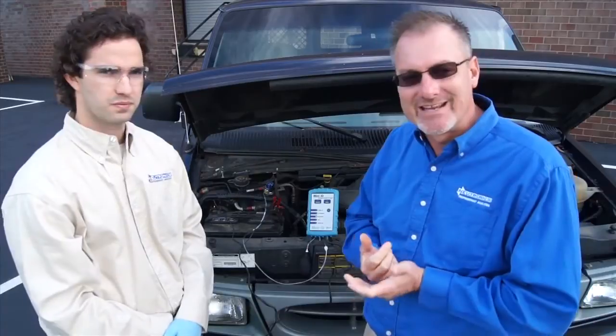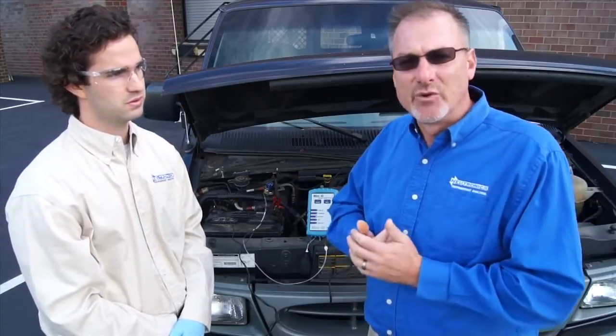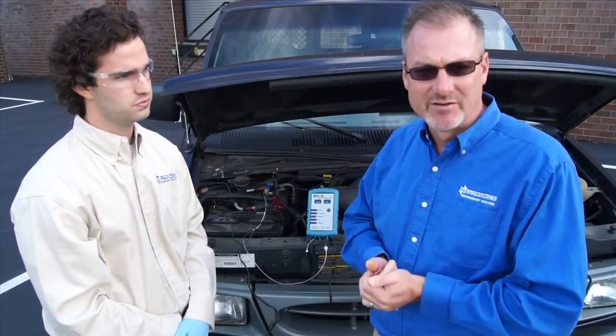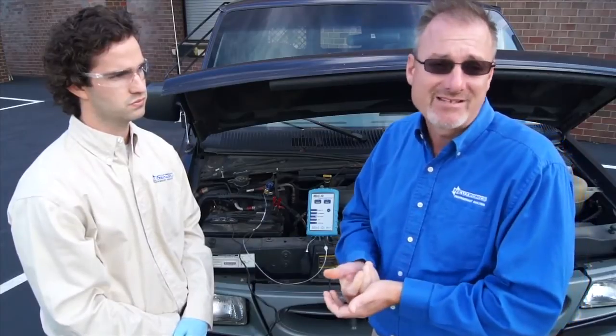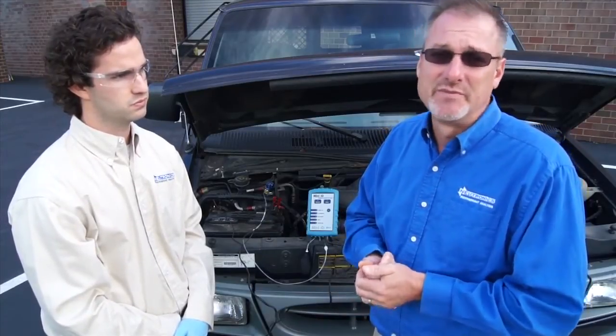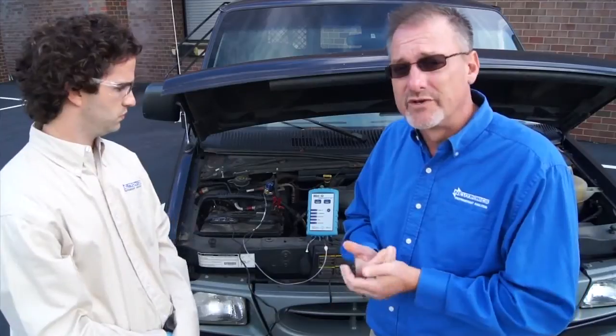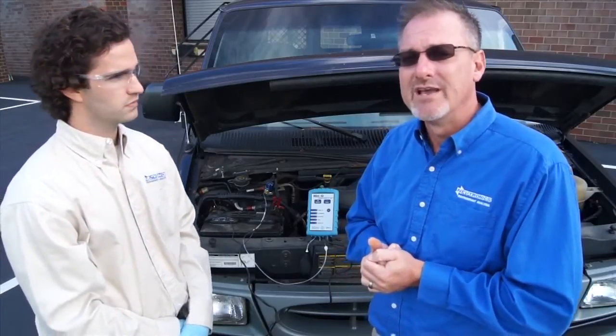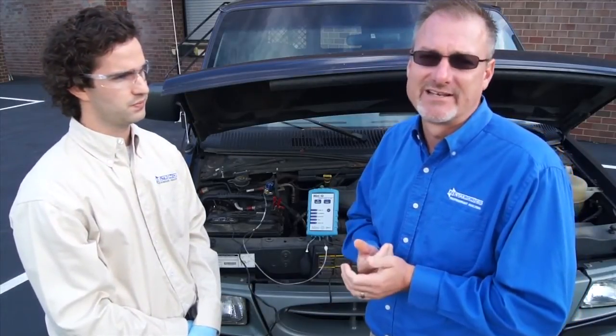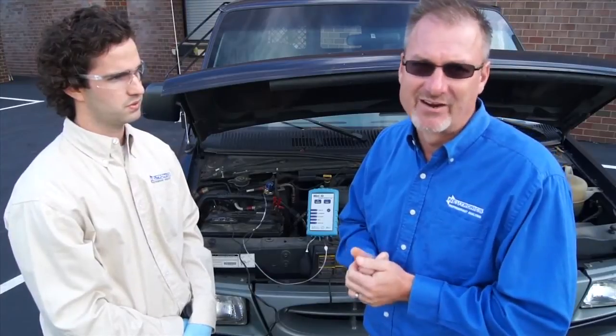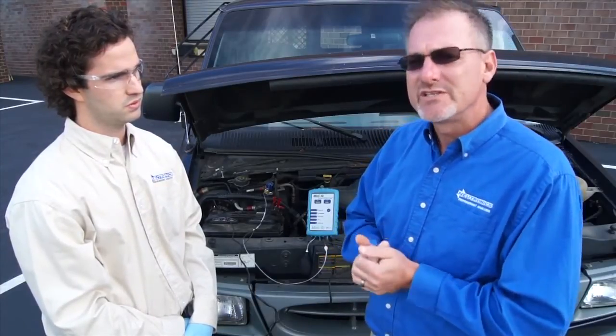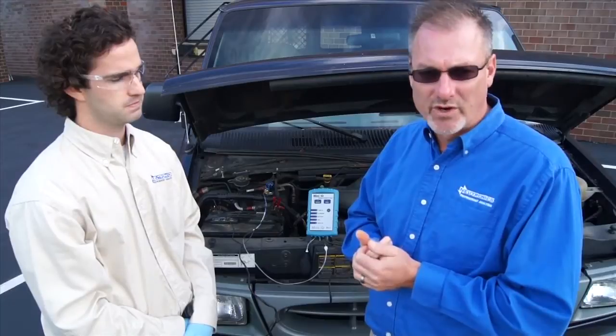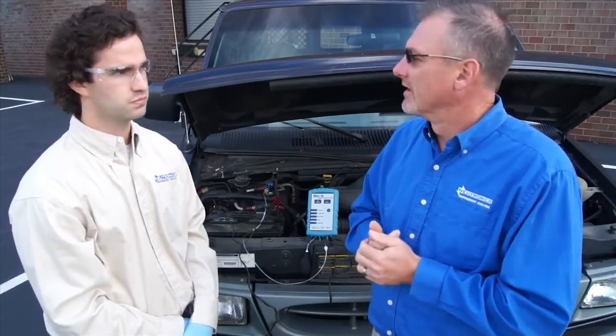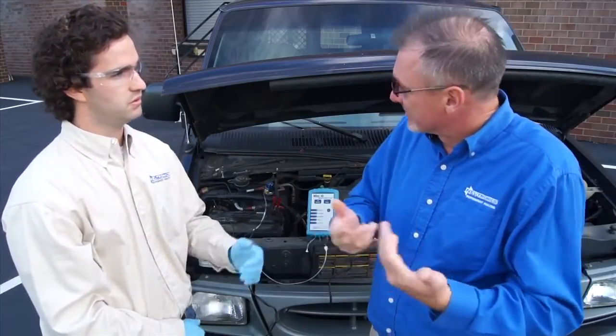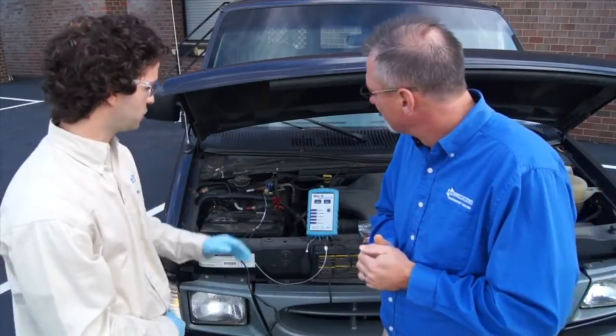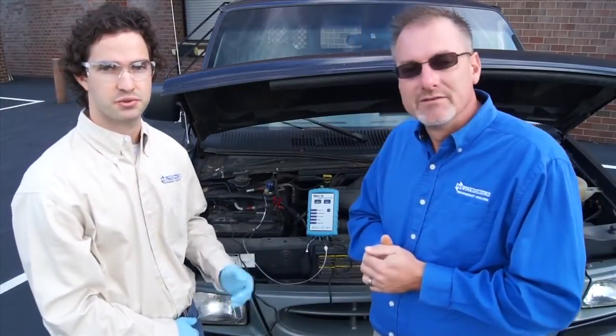If you get an excess air light, that means that there was just so much air in the system that you may get a pass with excess air, which means there was too much air, but the only refrigerant that was there was good 134A, or you could get a fail with excess air. If you get a fail with excess air, that means that the refrigerant we sampled wasn't good 134A, and you should treat it as such. Evacuate it with a separate machine. And it could also indicate that your restrictor is actually clogged and you need to replace that restrictor as well.